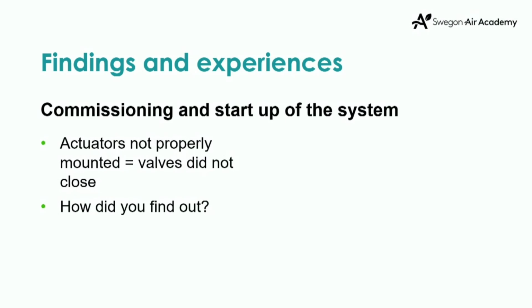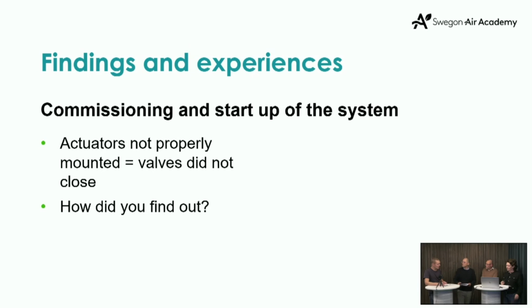We discovered that several actuators on the water side were not properly mounted, resulting in water valves that couldn't close. We discovered this as we saw the rooms were asking for cooling even in the middle of winter. And in some of the rooms, the room temperature was very high, which of course was a result of the valve not being in control of the water flow. So potentially a lot of energy waste and also annoyed tenants.